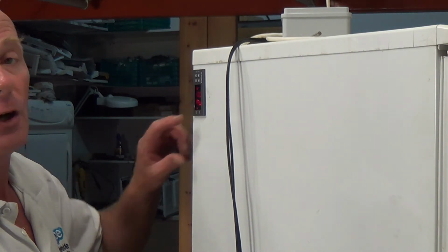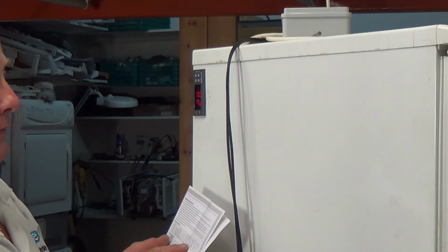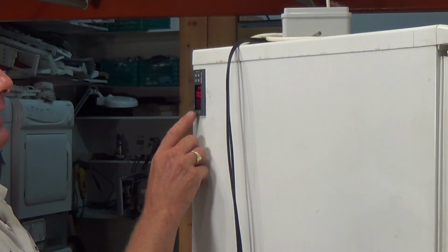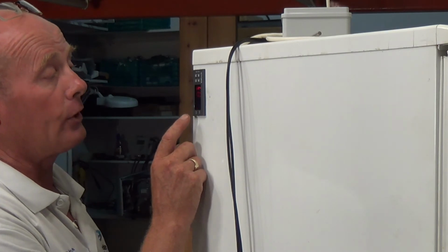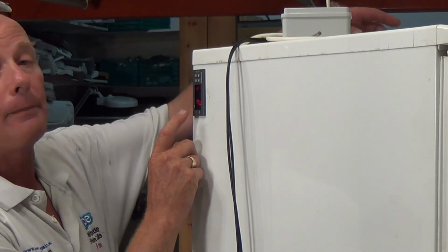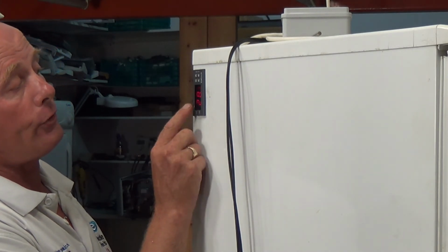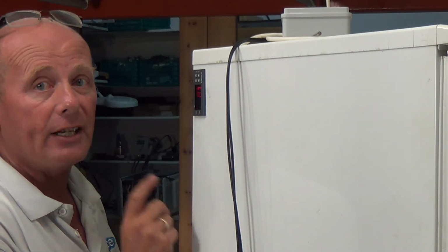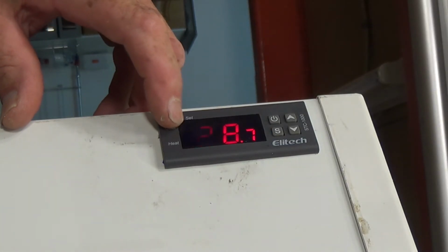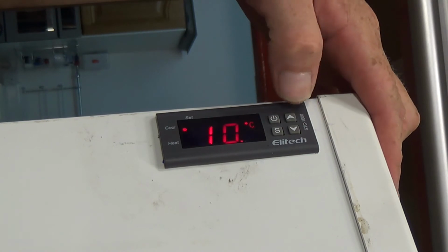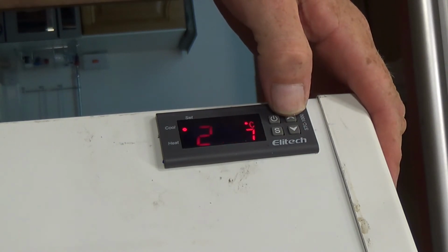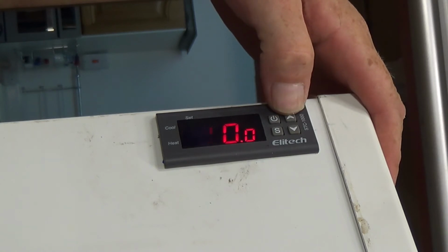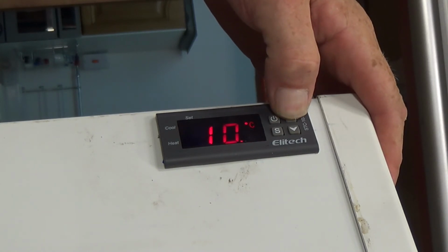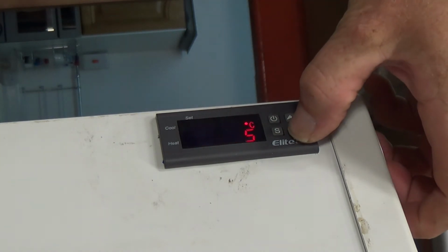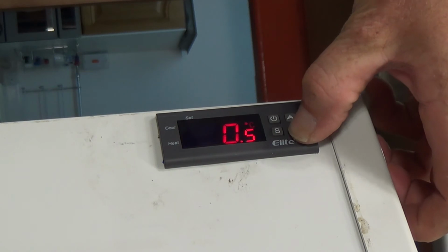Now the compressor is not going to start while this light is flashing for a couple of minutes, because the preset value according to the manual is 3 minutes. But I will show you how to set this up in a second. So let me move my camera so you can see what I'm doing, and we'll adjust the temperatures on this fridge. As you can see at the moment, it's 8.7 degrees in the refrigerator compartment. The compressor's not going to start for 3 minutes. It's set to start at plus 10 degrees, which will change in a minute, and our variation is 0.5. This is our differential.